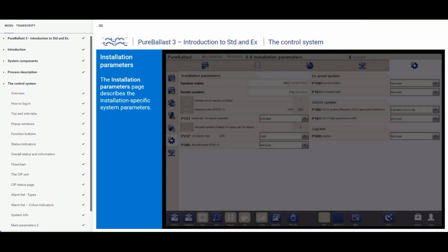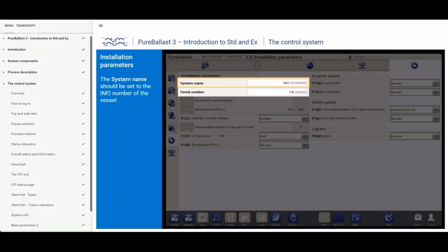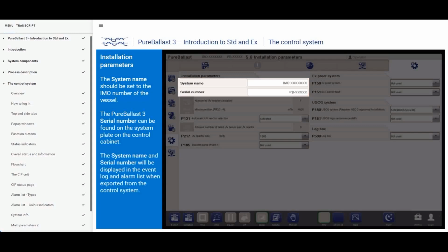The Installation Parameters page describes the installation-specific system parameters. Most parameters on this page are set at commissioning and should only be changed by Alfa Laval's service engineers. The system name should be set to the IMO number of the vessel. The Pure Ballast 3 serial number, starting with PB, can be found on the system plate on the electrical cabinet. The system name and serial number will be displayed in the event log and alarm list when exported from the control system. We have now reviewed the most frequently used pages for everyday operation. You can find additional information about the other pages in the system manual.